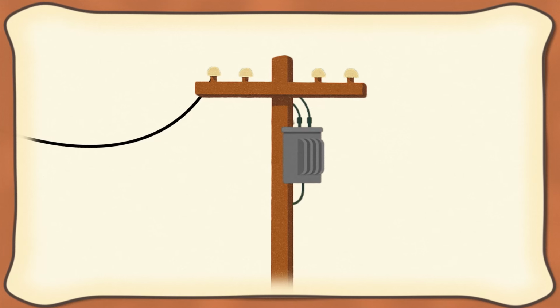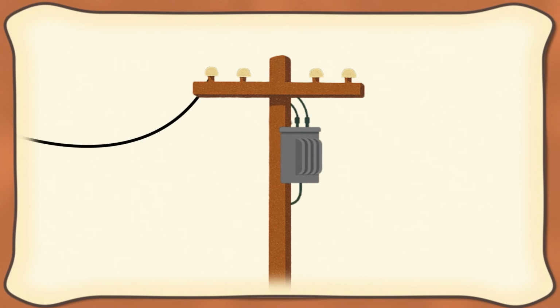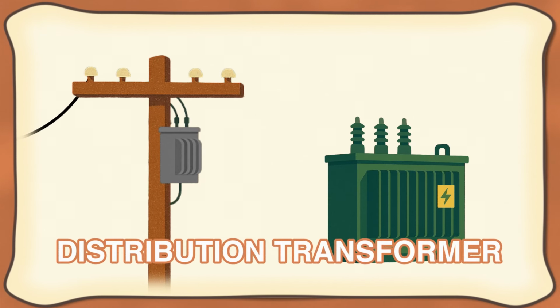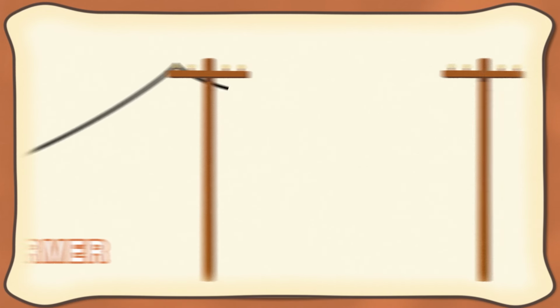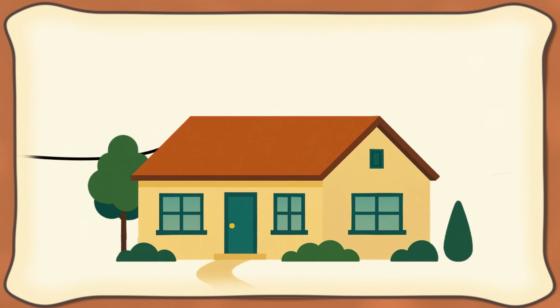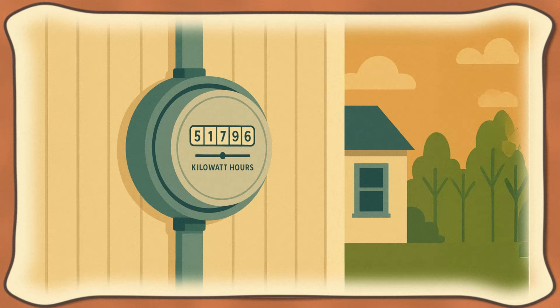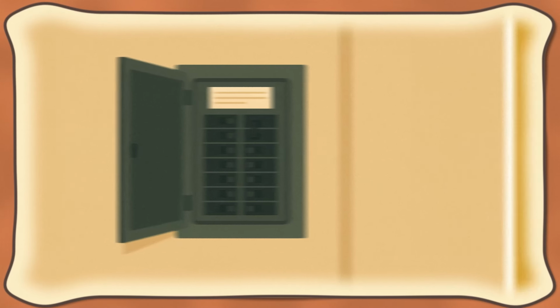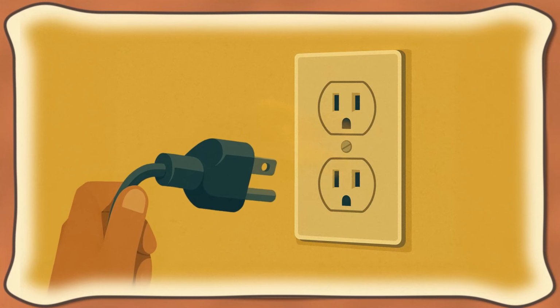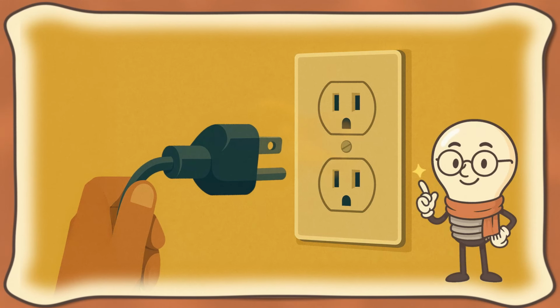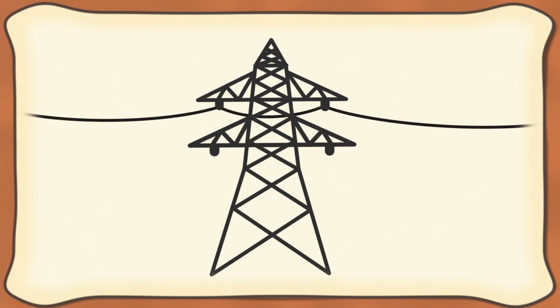Near the end of those lines sits a gray, can-shaped device on a pole or a green box on the ground. That's a distribution transformer. It's the last voltage drop, turning thousands of volts into the 120 or 240 volts that your home appliances can use safely. From that transformer, short service lines run to your house, into a meter box that measures your usage, through your breaker panel, and finally into the outlets and light switches you use every day. So when you flip a switch, you're completing a journey that started miles away, from generator to transmission tower to substation to transformer to your wall.